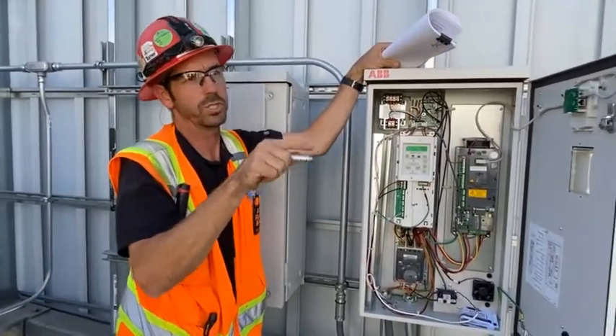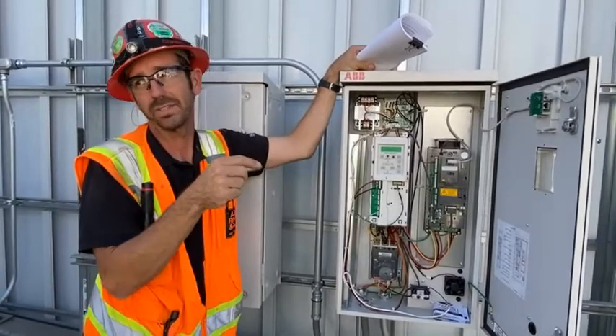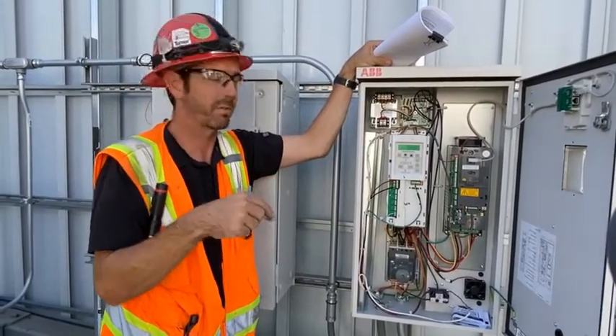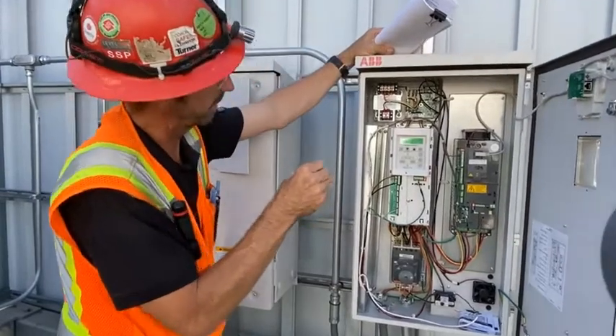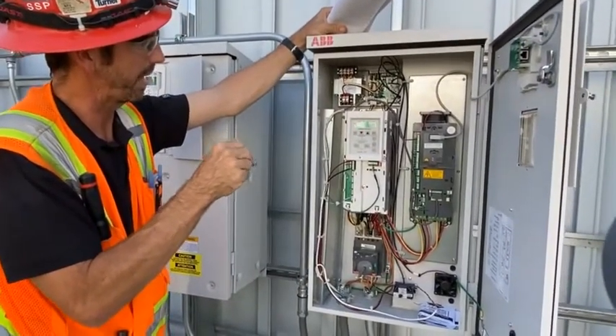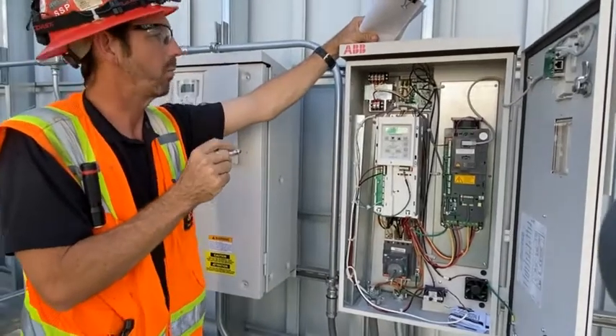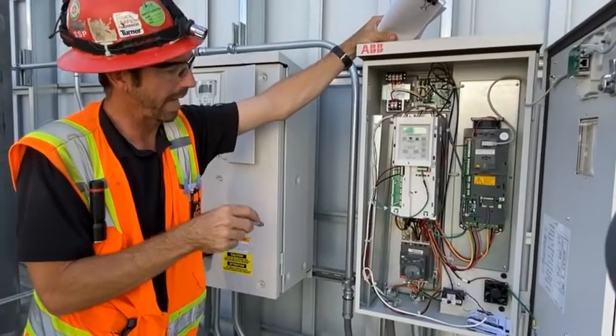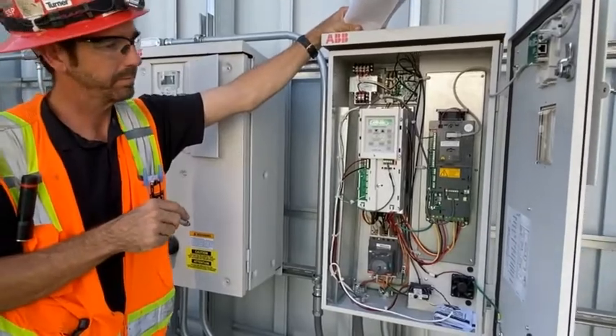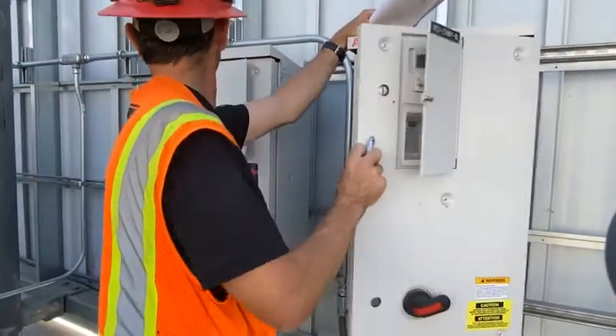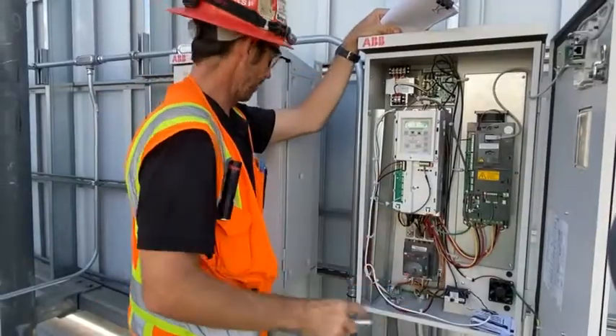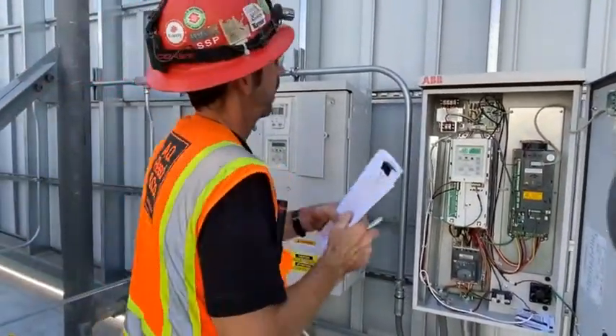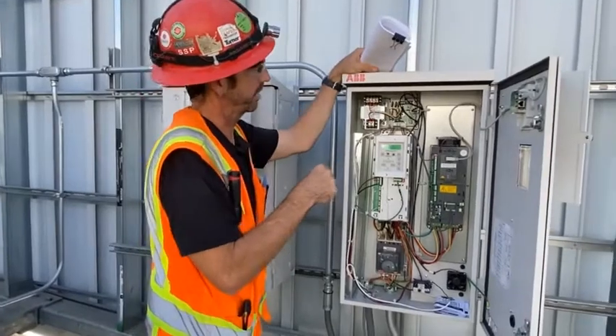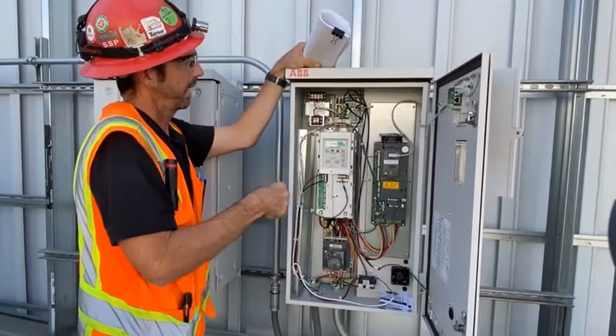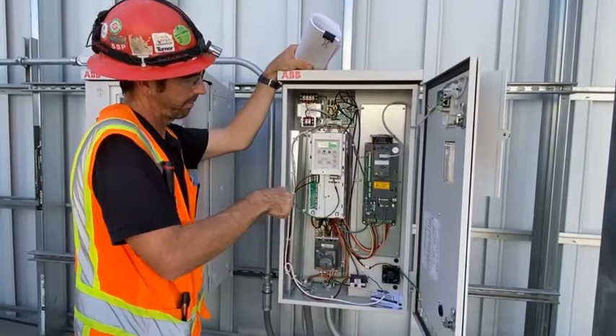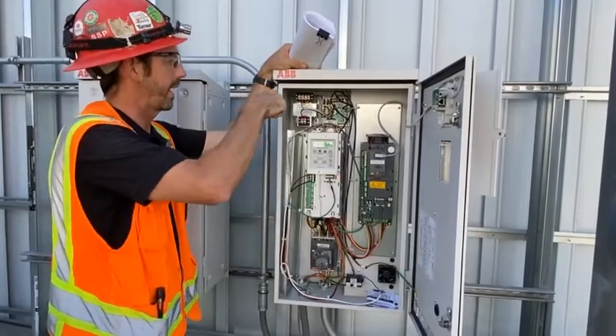So when you choose bypass or drive, it'll pull in different sets of contactors to operate in drive or bypass mode. That's all behind this interface right here, the Eclipse bypass panel. Once a year, you want to shut off the power at the main breaker and check the tightness of lugs, and as needed, if there were a buildup of dust or material in here, you'd want to use dry nitrogen and blow that down.